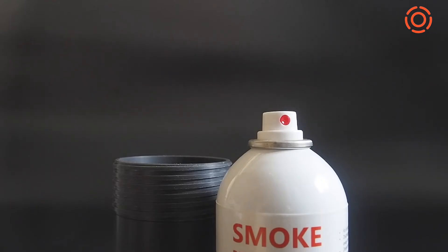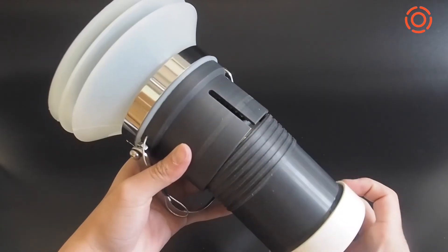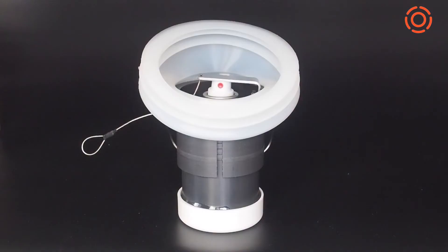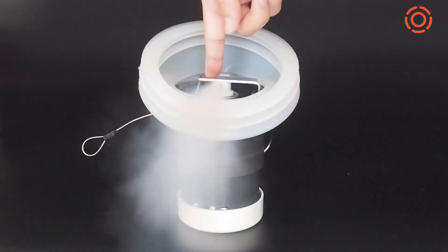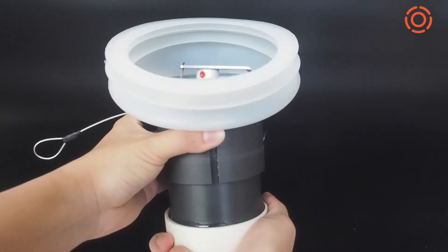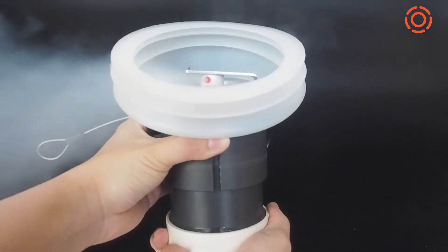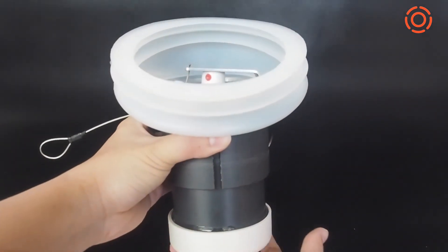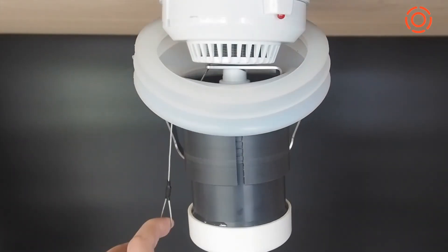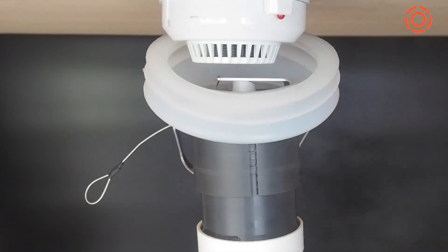There is no need to pull out the spray head. Adjust the holder until the canned smoke can be sprayed by a light press. Twist it tighter if it requires a lighter press, such as when testing detectors on light ceiling boards.